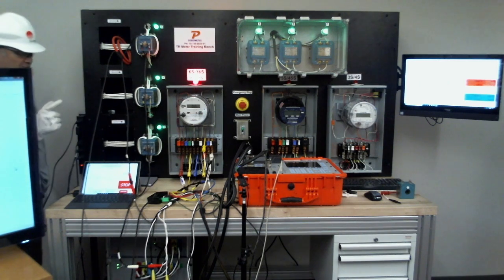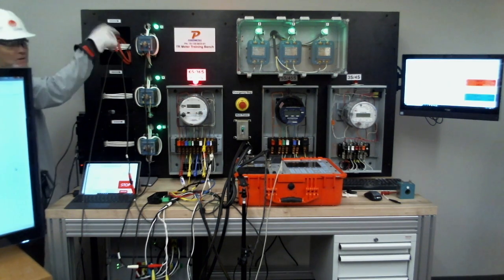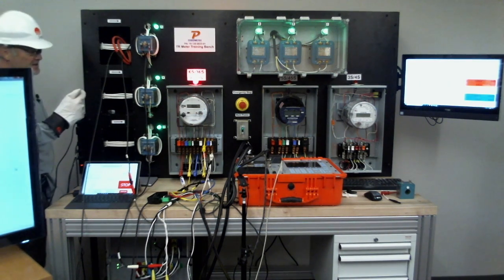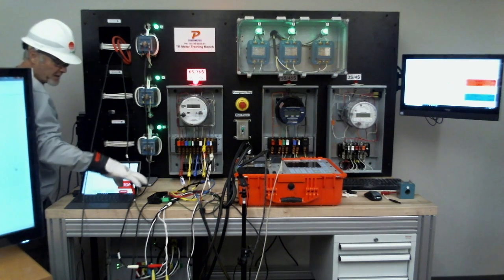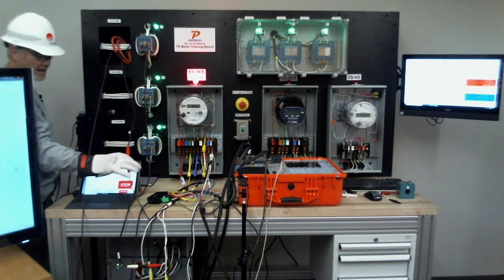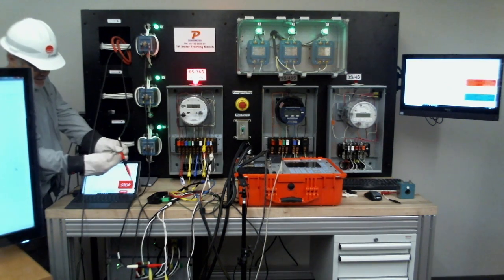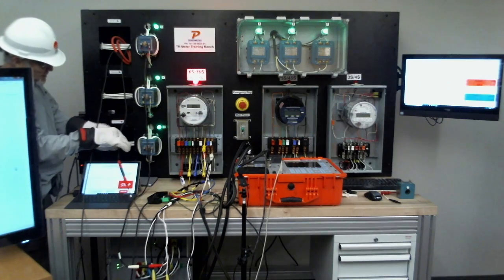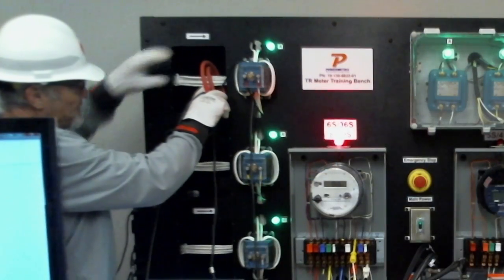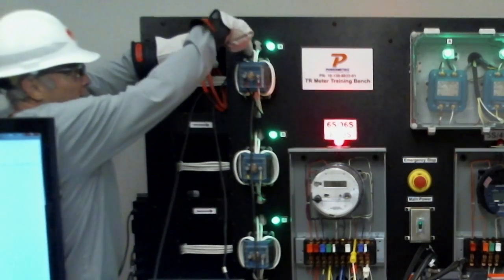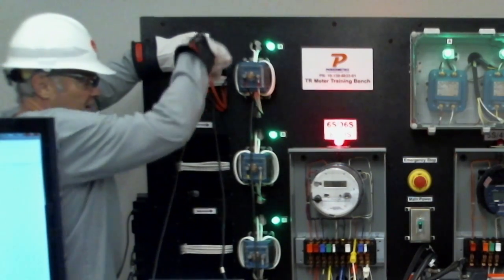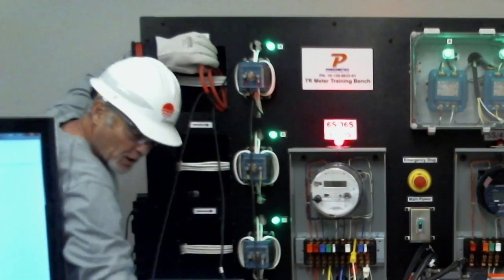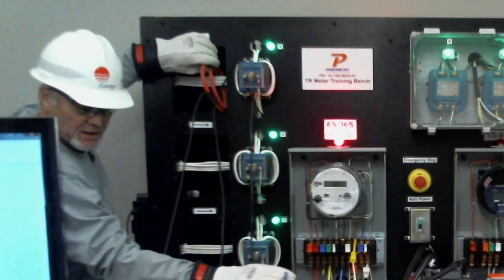I don't care which way you thread it through or work it through that CT, I just need to know that this drive end is going to drive the current. So the current comes up, goes through my flex, comes in on the dot side of that CT, and then comes back through the return, making my return connection over here.